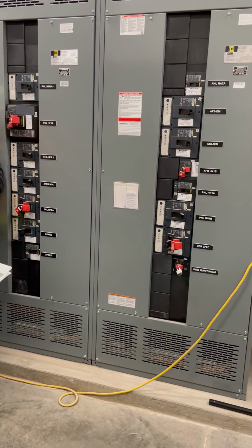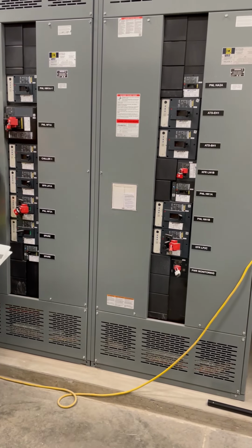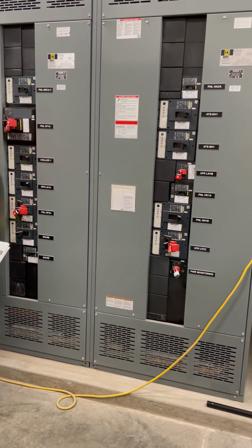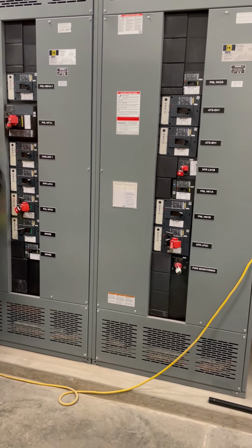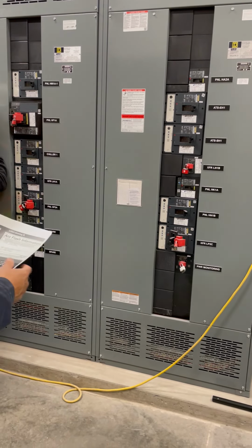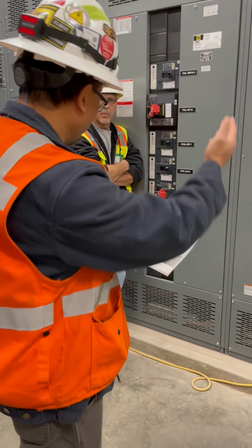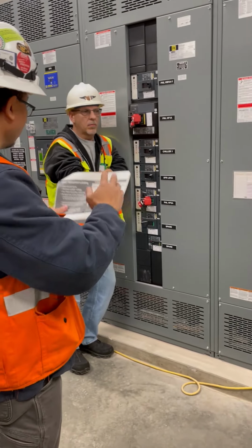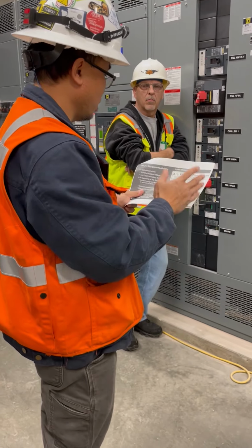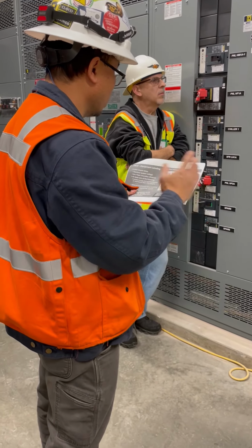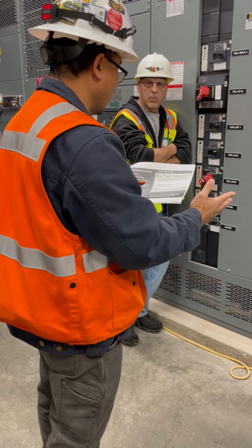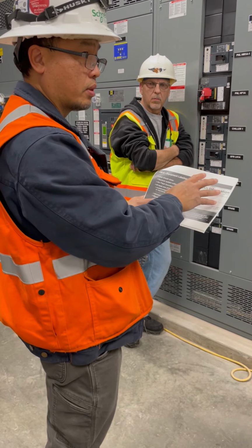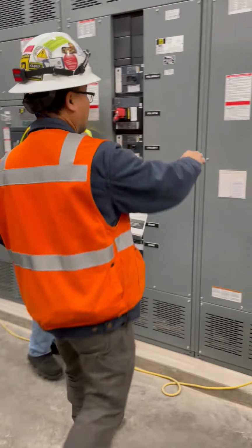When you turn all the lights on, all the building on, all the loads on, if they're not set correctly, you could have issues. Okay, so we'll get to the arc flash label here. Once we do all that study, analyze all the information, and we agree on what the setting should be, and once you set all that, we get a label. We develop this label here, and here's that label.